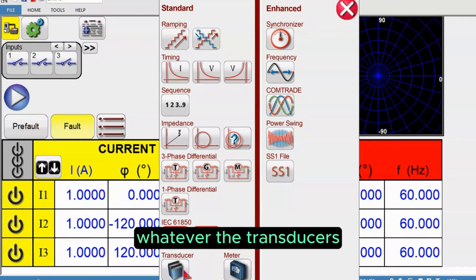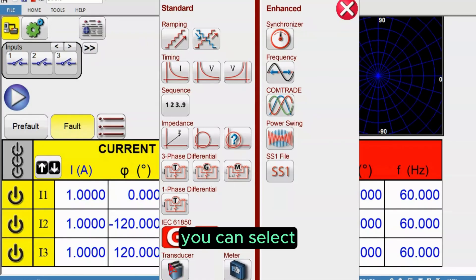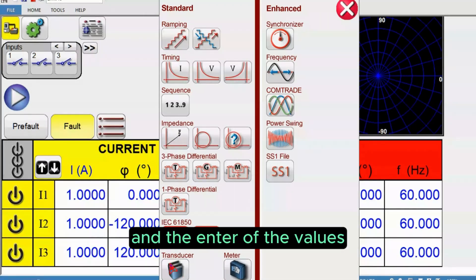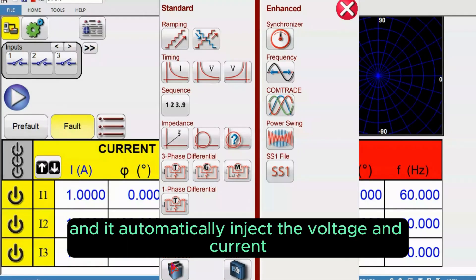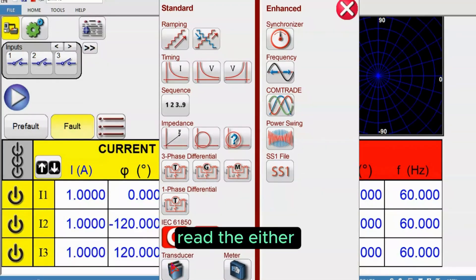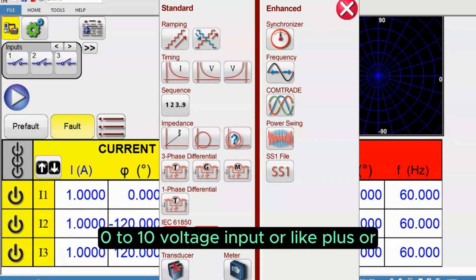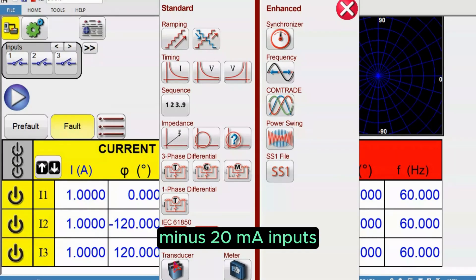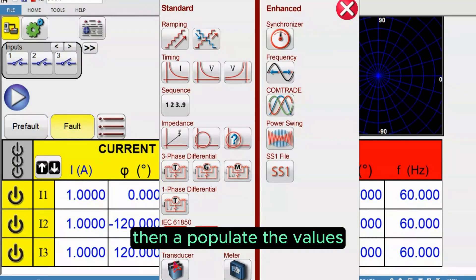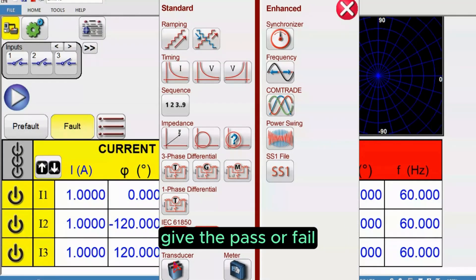This is a predefined module where you can select a frequency transducer, power transducer, or whatever transducers you want. Enter the values and it automatically injects voltage and current, reads either zero to ten voltage input or plus or minus 20 milliamps input, then populates the values and gives pass or fail results.